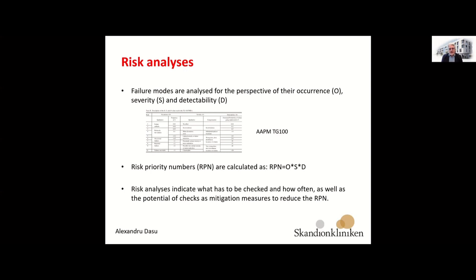So based on the occurrence, severity, and detectability, one calculates a so-called risk priority number, which is the product of all these factors. And naturally, based on the risk analysis, one identifies those failure modes which are most likely to have a high risk priority. And that means those that have to be checked, or highlights the checks that have to be done, how often they have to be done in order to mitigate the failure and the consequences, as well as what is the potential of the checks as a mitigation measure to reduce these risk priority numbers. So in a way, this process gives you an indication of what to measure, when to measure, and how important it is that you focus on one parameter in comparison to another one.